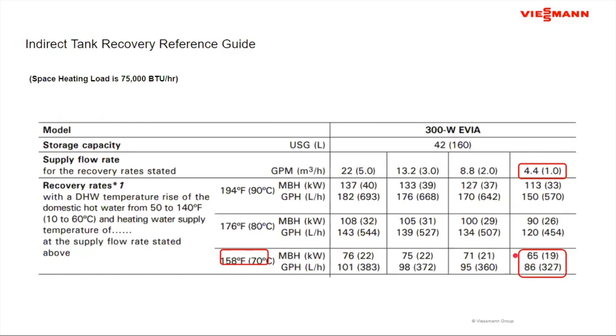So the question then becomes, do I need to upsize the boiler? And if so, how much? Okay. The first answer is, if I'm doing priority, I don't. If I have 75,000 BTUs per hour available and I now only need 33, if I'm doing priority, I'm not going to upsize the boiler. I'm going to run off of priority. I'm going to be able to put 65,000 out of the 75 into that water heater, quickly recover it, and I'm going to have more than enough hot water that's needed. Okay.